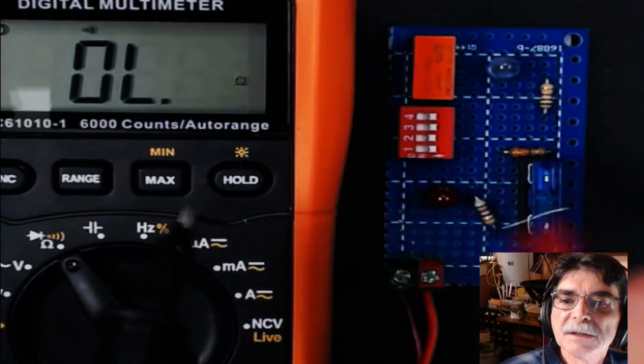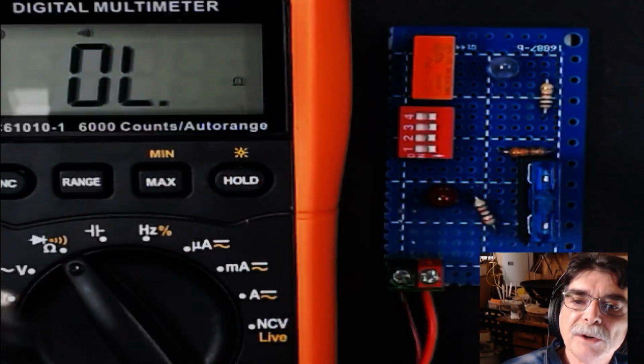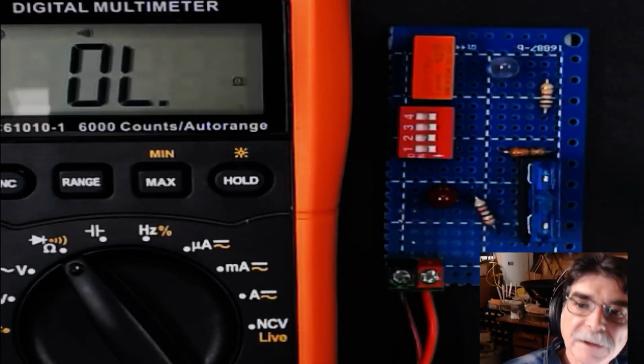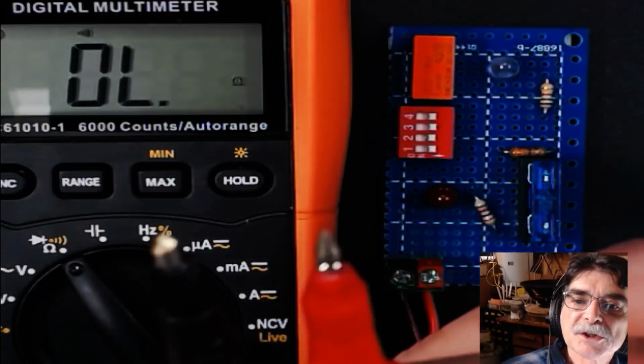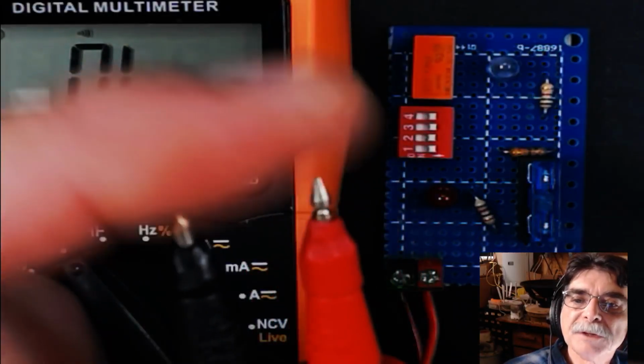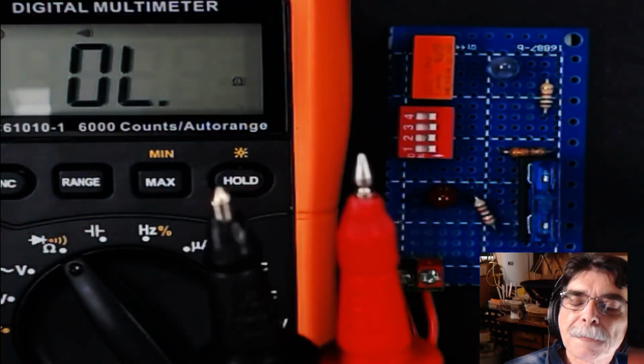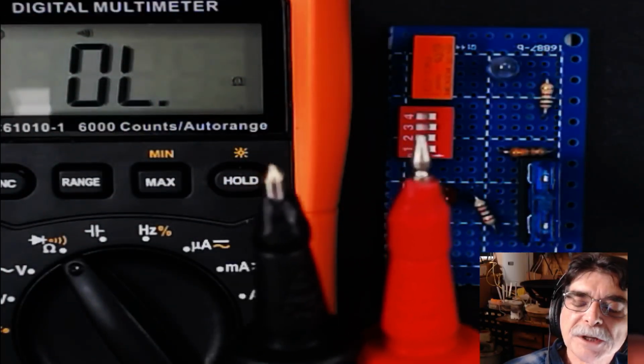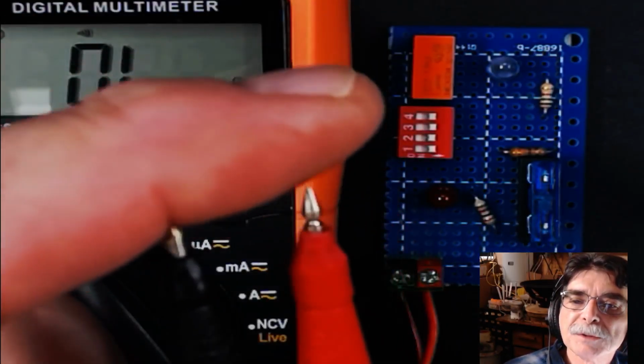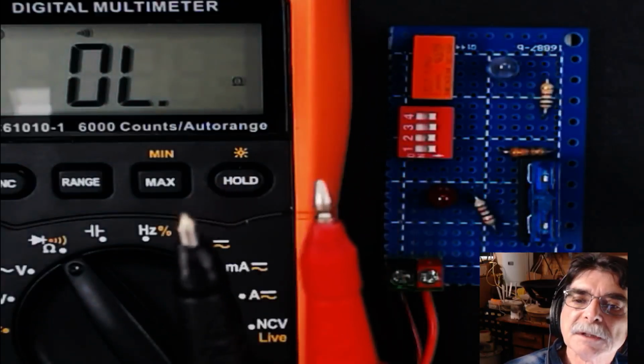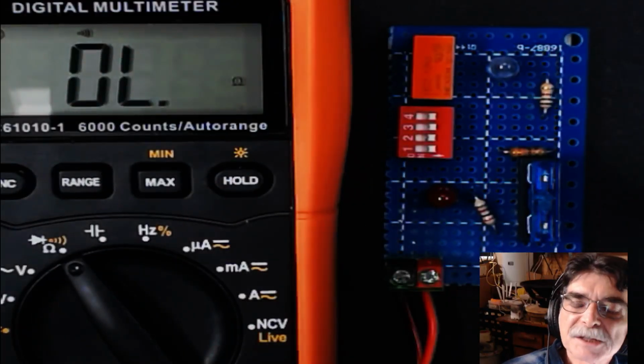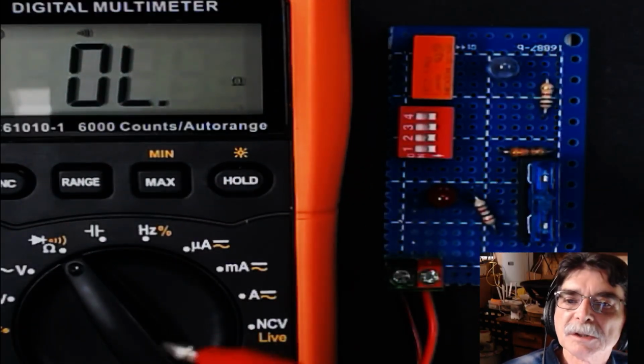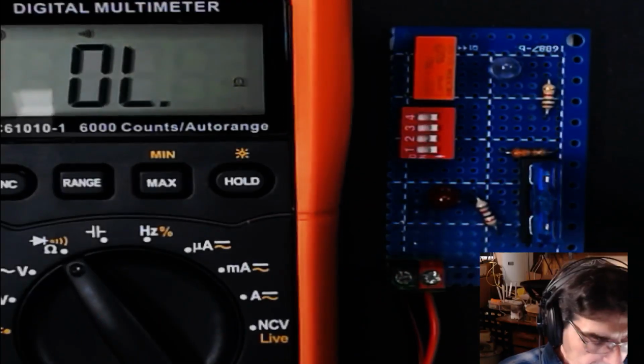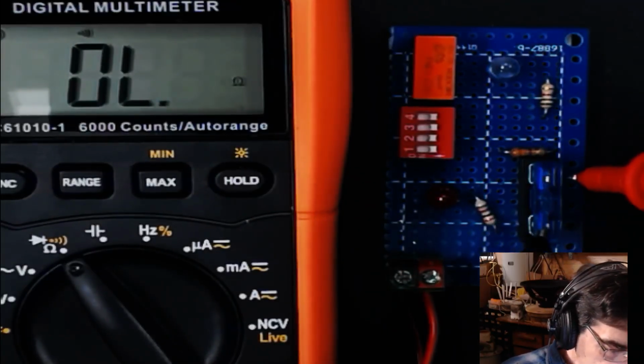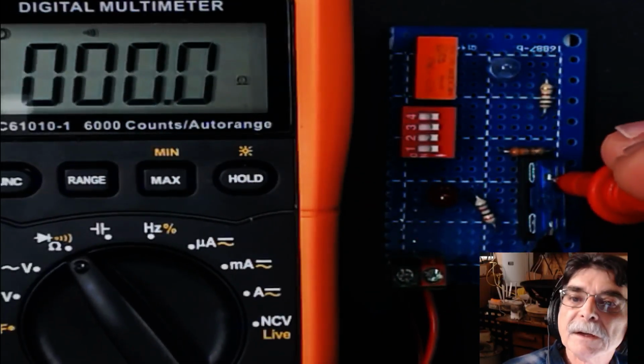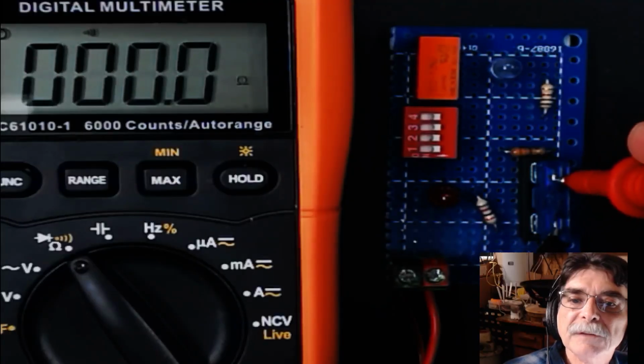And the reason is that in continuity mode, a digital voltmeter actually sends a small voltage out these two probes. So if I were to put another meter onto those probes, I would read 3 volts. So the meter's not expecting to see voltage when you're in continuity mode. So if the circuit is energized, it will show a short even though the fuse is open.